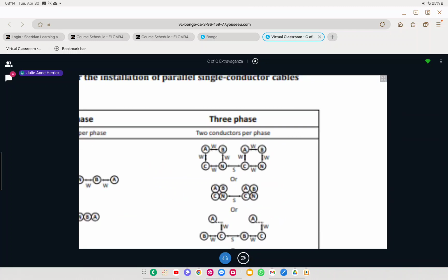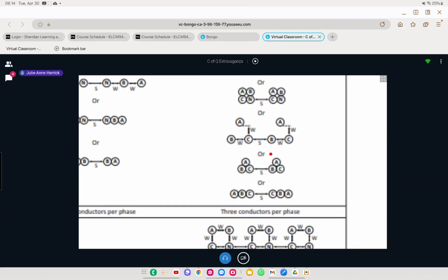With this 3-phase, 2 conductors per phase running in parallel, this is how they're going to be buried — phase A, B, and C with the neutral separated. That's what the S is, and then A, B, C with the neutral right there. You may get a question based off of that.